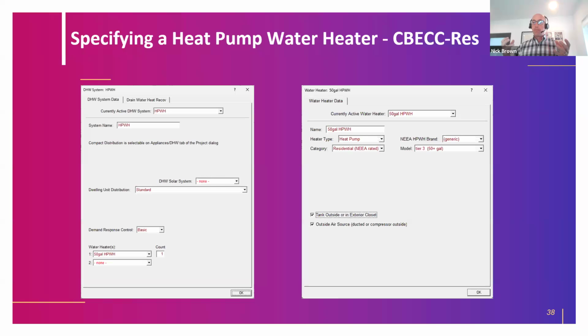Because heat pumps heat the water by taking heat from the air around them, they're not generating every BTU of heat by burning gas or using electricity. So the temperature of the air around the heat pump water heater has a big impact on its efficiency. If we tell the software we're putting this outside, in a garage, or inside conditioned space, that's going to affect the efficiency of the heat pump water heater. For that reason, you never have to say where you're putting your gas water heater, but you do have to say where you're putting your heat pump water heater.